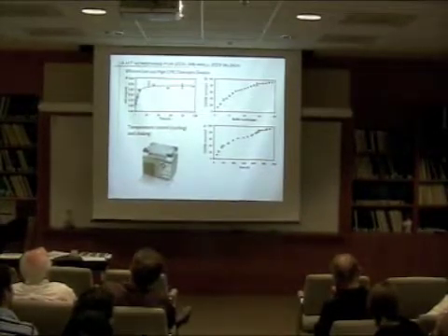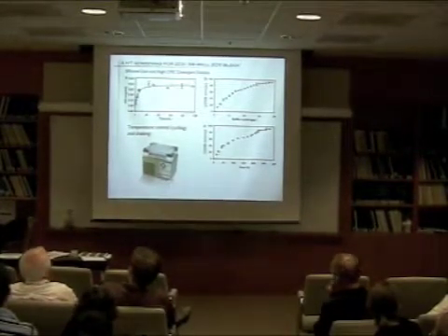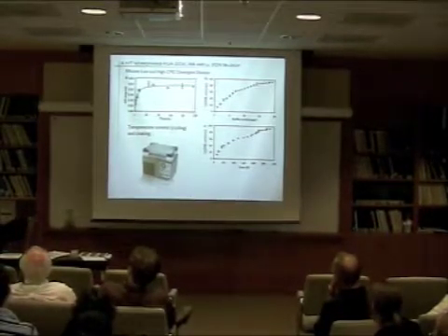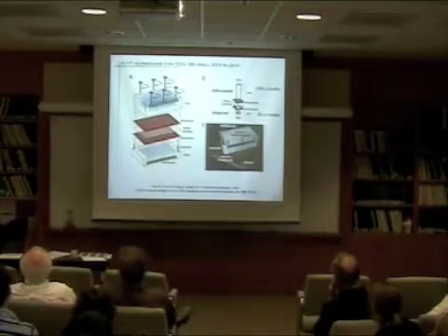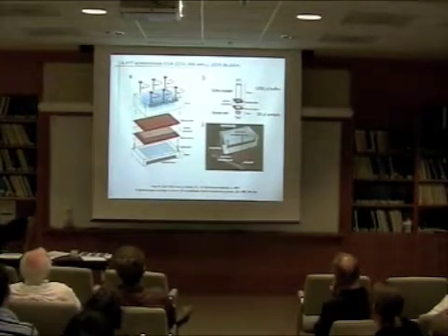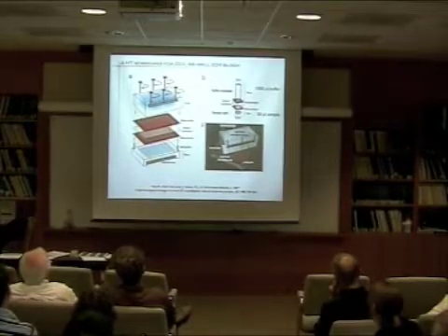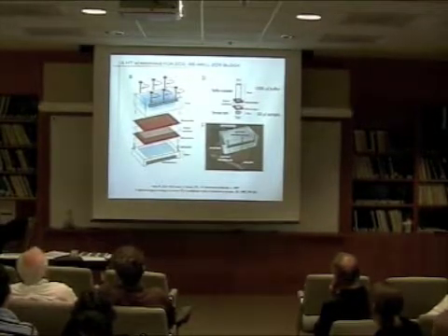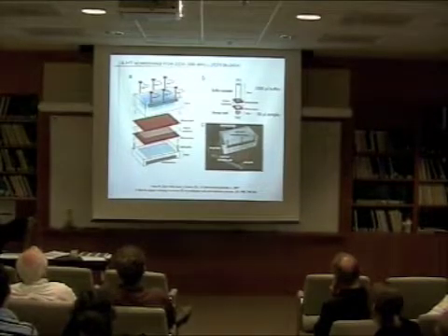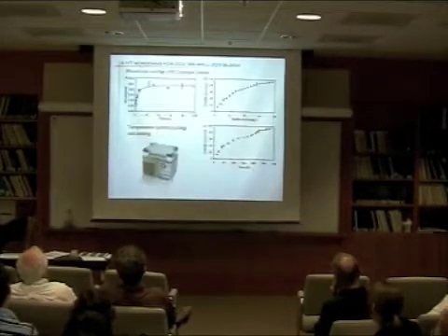How do you exchange it? By hand? By hand. You can either use a robot, or you can use an 8-channel pipette, which almost any lab has. And something else I forgot to say is that the idea of these chambers is that you can use 96 different buffers here. So you are not restricted to one single dialysis buffer as some other systems are.